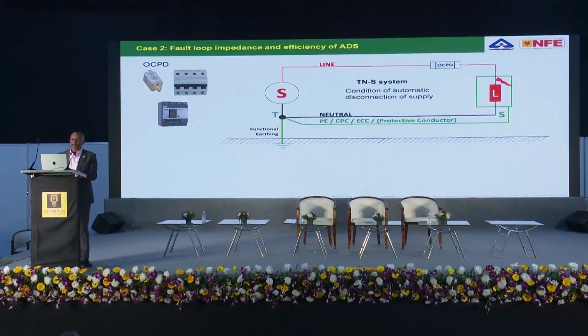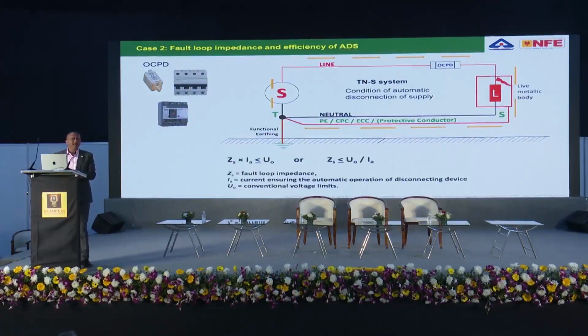Now there is a fault. The fault current will circulate in this loop. The impedance of the loop decides the amount of current, and the amount of current decides the disconnection time. Very simple. Each and every device has its own tripping characteristics. For example, a type C MCB, for instantaneous tripping, needs 10 times the rated current. So a 63 amp MCB, if the current is 10 times, meaning 630 amps or more, then only it will trip in 200 milliseconds. So what should we do?